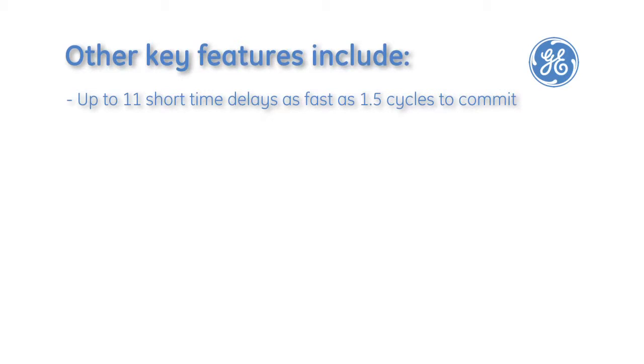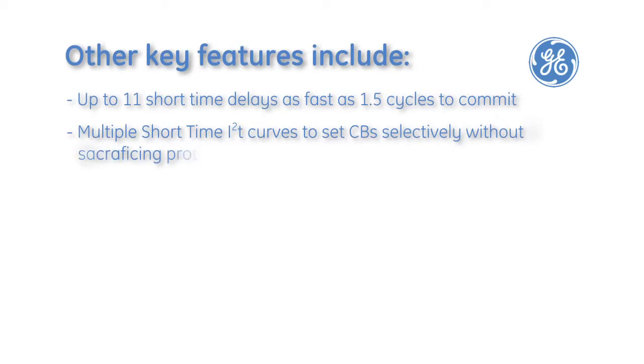Other key features include up to 11 short time delays as fast as one and a half cycles to commit, and multiple short time I-squared-T curves to set circuit breaker selectivity without sacrificing protection.